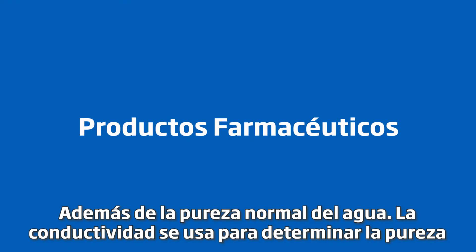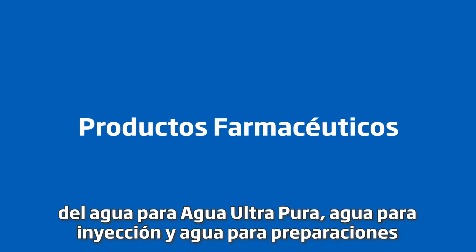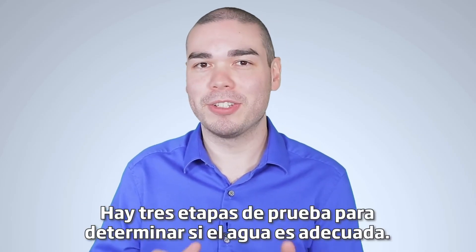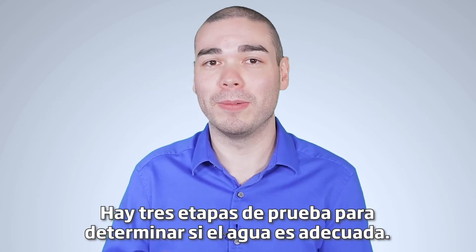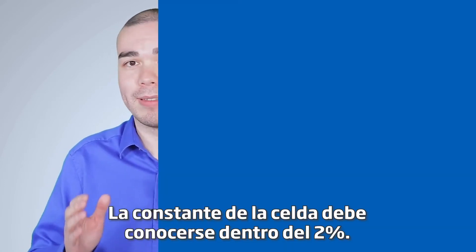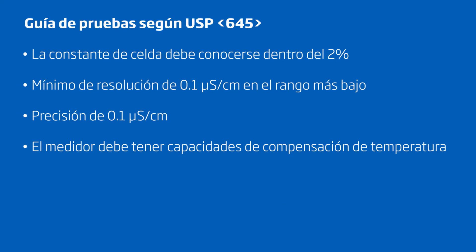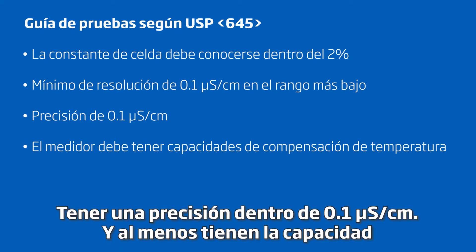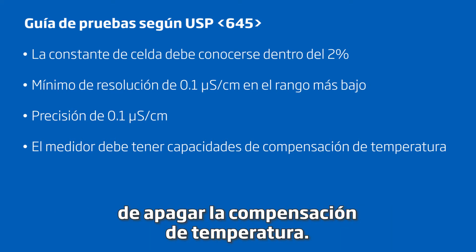Besides normal water purity, conductivity is used to determine water purity for ultra-pure water, water for injection, and water for drug preparations. There are three stages of testing to determine if the water is suitable. The stages have very strict parameters, including the cell constant must be known within two percent, a minimum resolution of 0.1 microsiemens per centimeter at the lowest range, an accuracy of within 0.1 microsiemens per centimeter, and at least the ability to shut off temperature compensation.